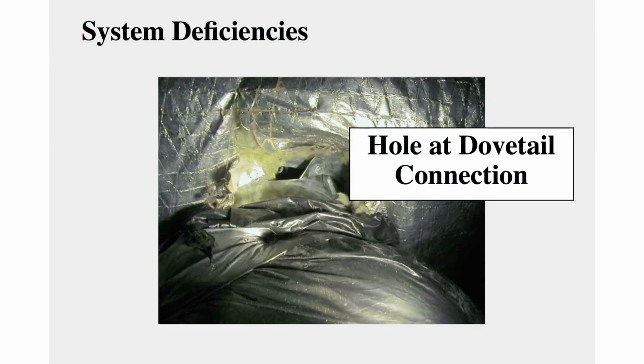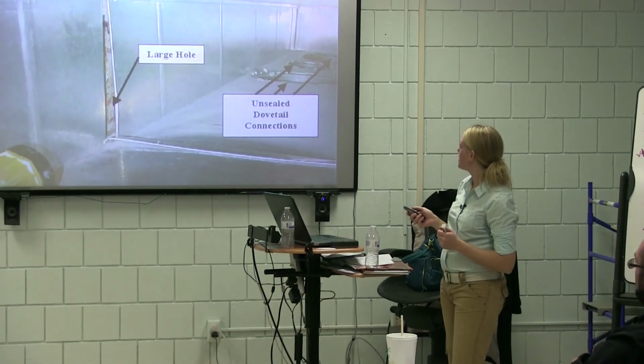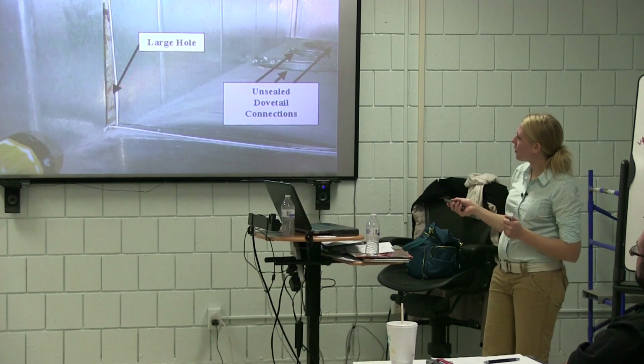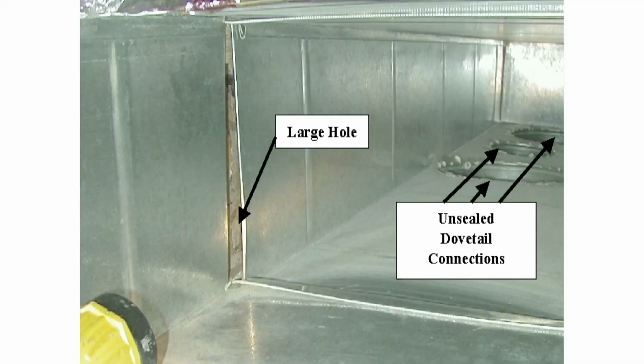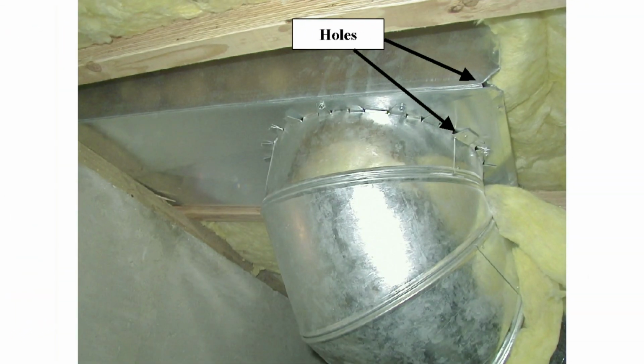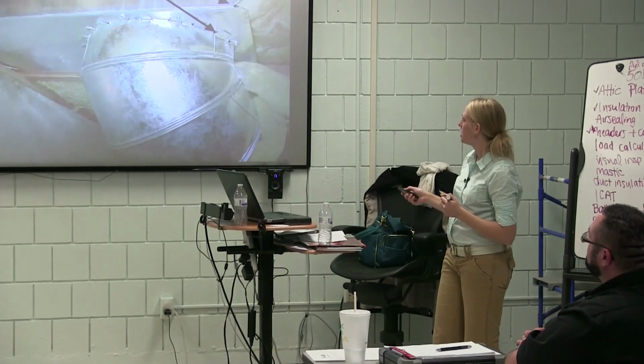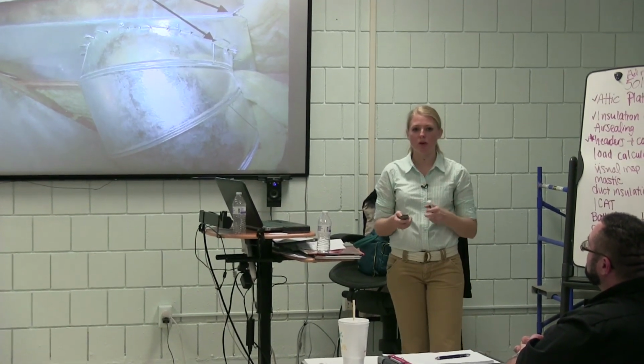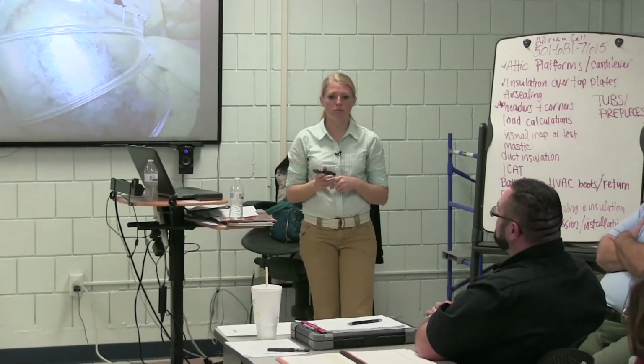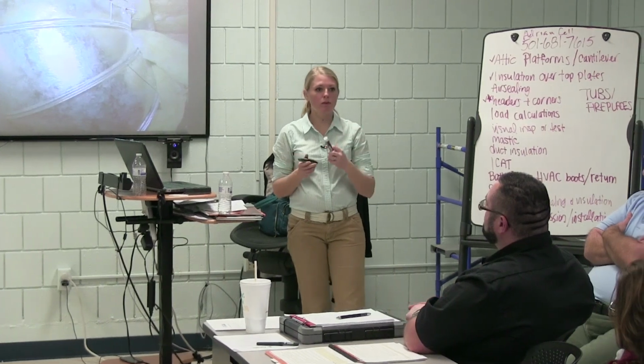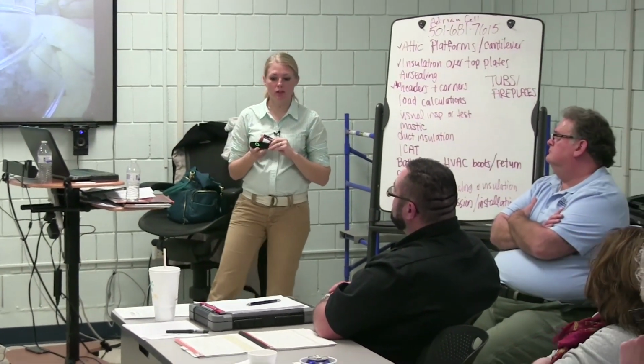Why are we talking about sealing up ducts? Well, this is why. We've got a nice little hole right here. In this case, we've got a bunch of holes in this system, so that's why we're talking about sealing things up properly, making sure that these holes don't exist. A bunch of holes right here, that's just air that's pouring out into that attic. Ron was saying 42% leakage.